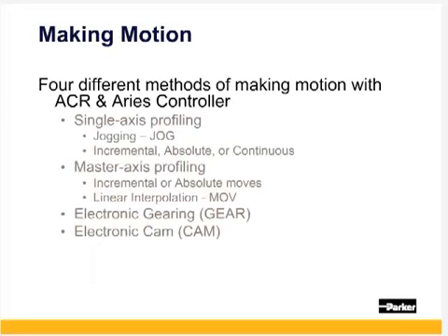The ACR and Aries controller allows four different types of motion. Single axis moves are done with the JOG — these can be incremental or absolute distance commands or continuous velocity moves. Interpolated or coordinated moves use the master axis profiling and allow multi-axis moves. Gearing and caming can also be programmed, but will be covered in the advanced motion training.